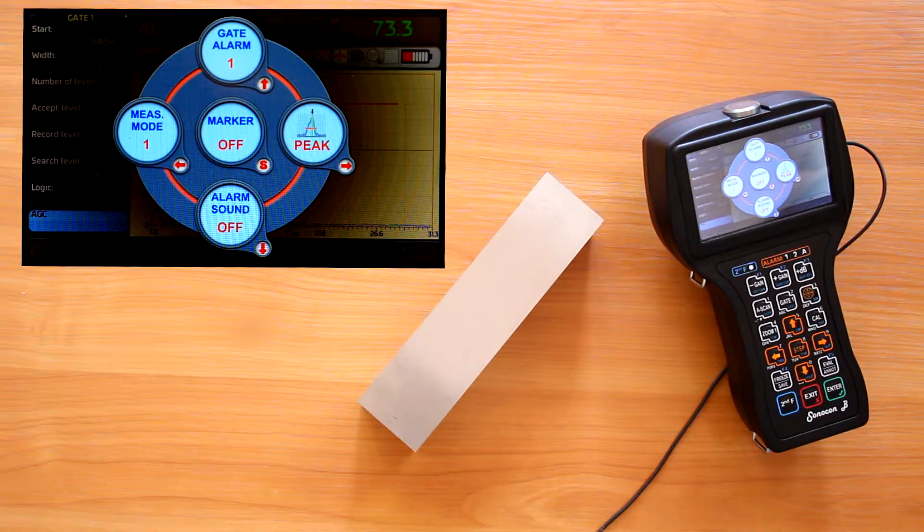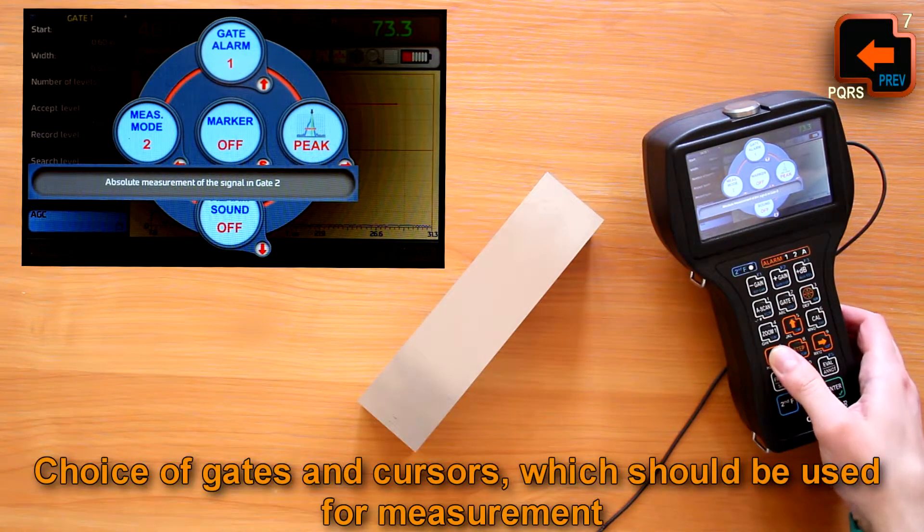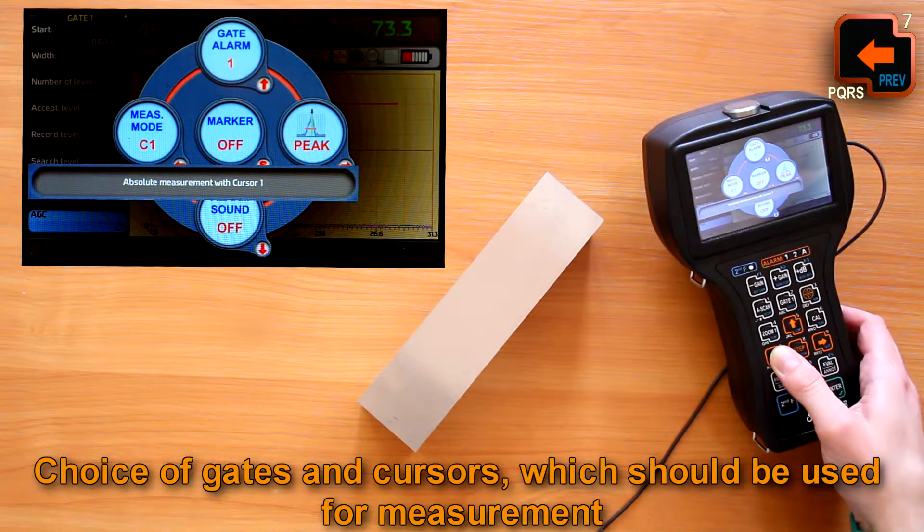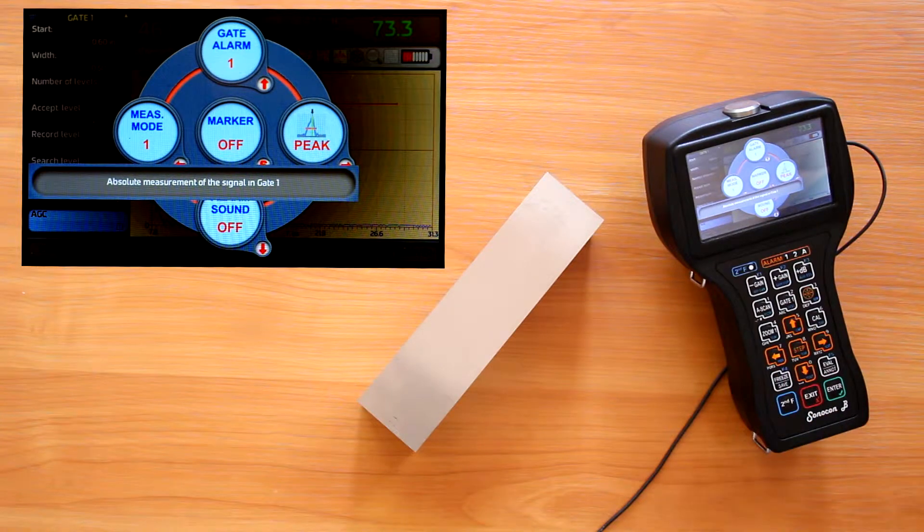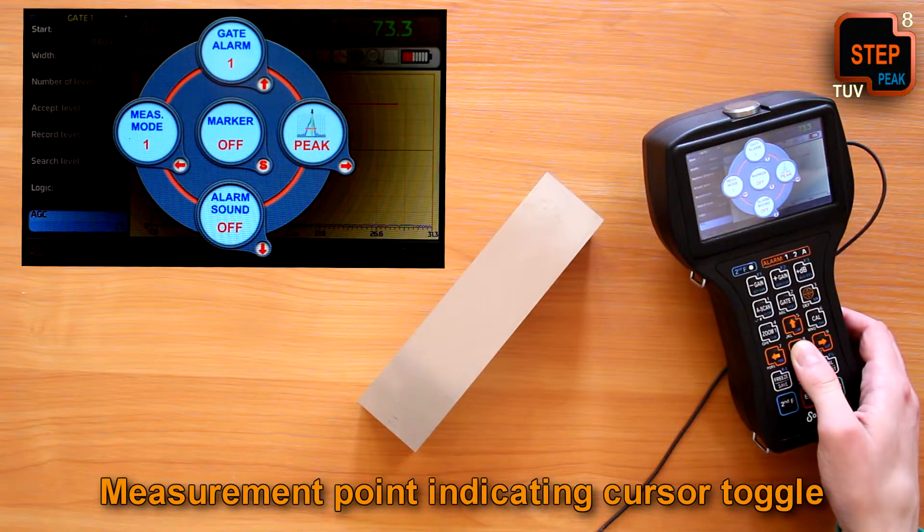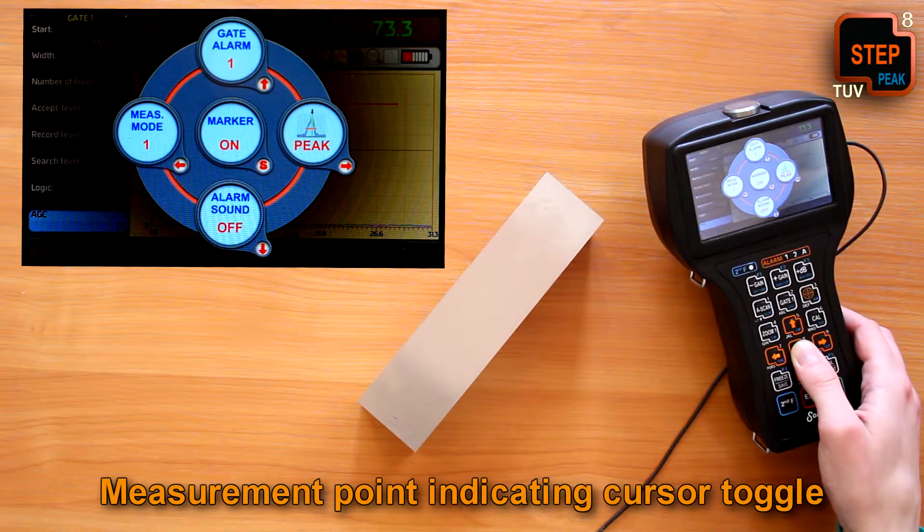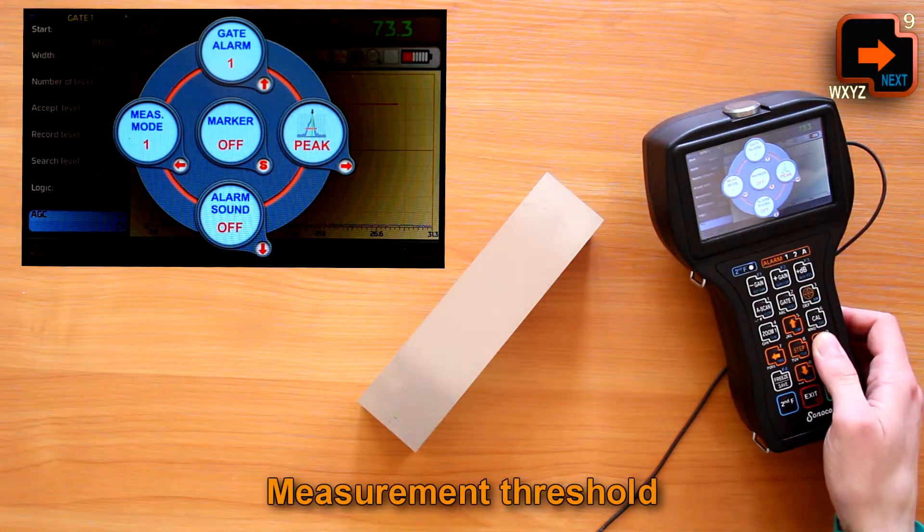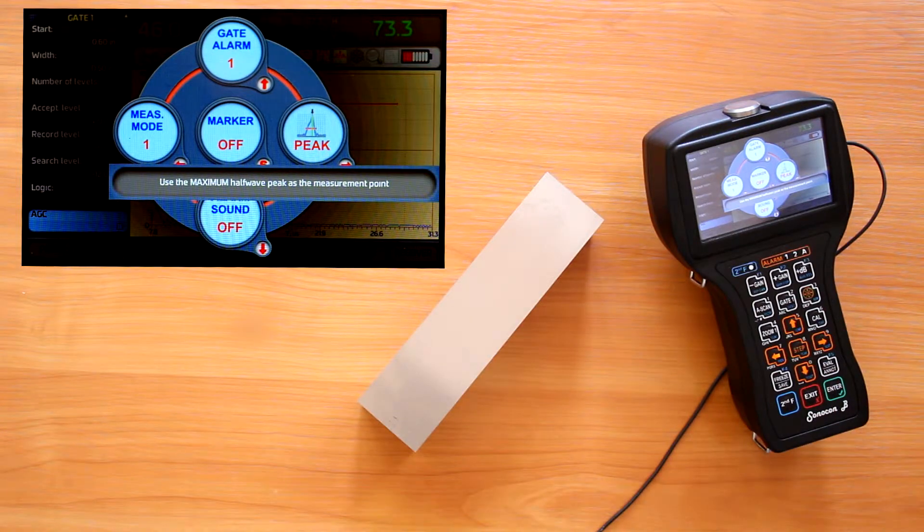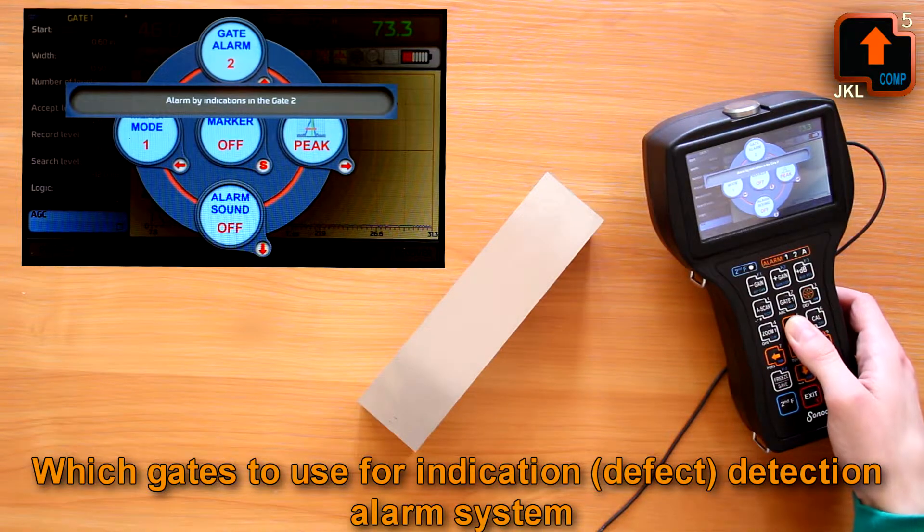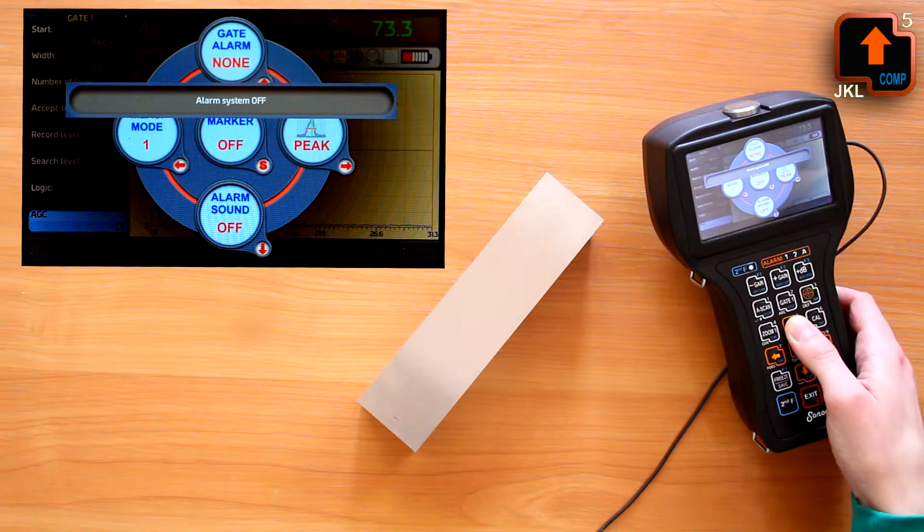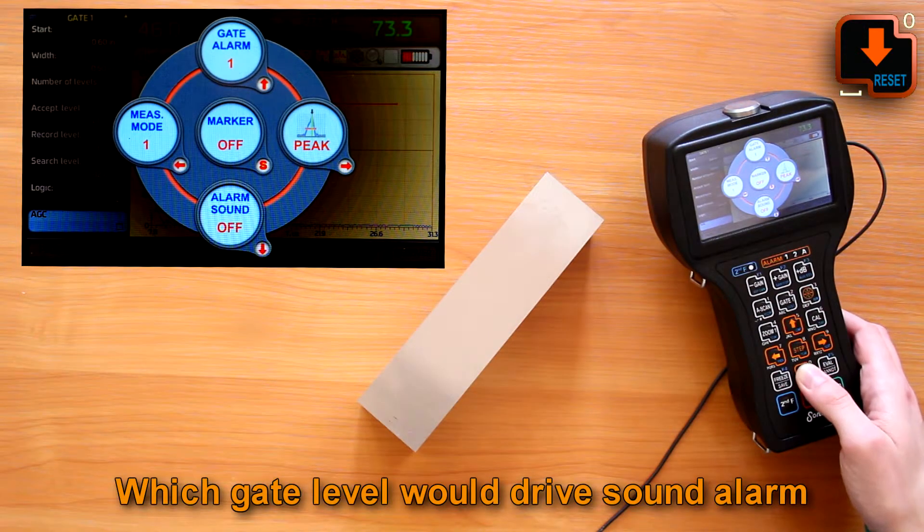First page is dedicated to the measurement and alarm settings. The choice of the gates and cursors which should be used for measurement. Measurement point indicating cursor toggle. Measurement threshold peak or edge. Which gates to use for indication detection alarm system. Which gate level would drive sound alarm.